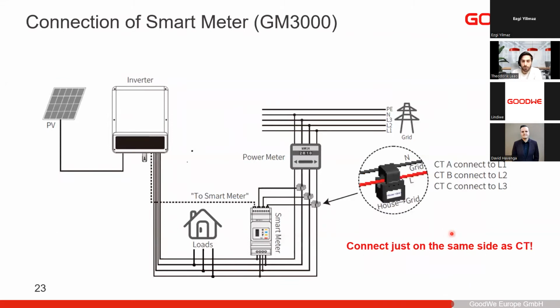It is now important to know where to place the smart meter. The smart meter itself can, of course, be placed with the inverter in the AC box that you have, but the cables from the meter need to be attached at the proper points in the installation. So here on the top side you have the current clamps, and these come with the smart meter and they're already pre-wired, so you don't need to think about this too much. On the CT clamps you also have letters saying A, B and C. This stands for the different phases. So phase 1 is A, phase 2 is B, and phase 3 is C. Make sure that you connect them properly, and you see here the direction of the CTs. On the CTs, there's also an arrow saying house to grid, and this arrow should then point towards the grid from the house.